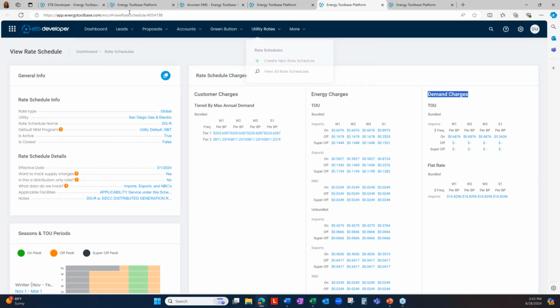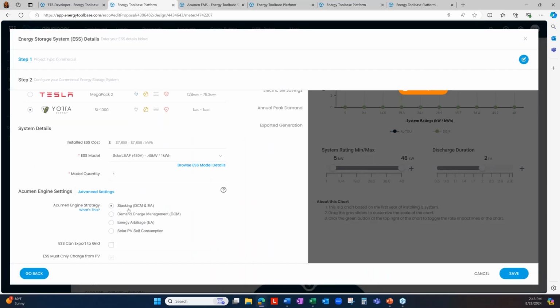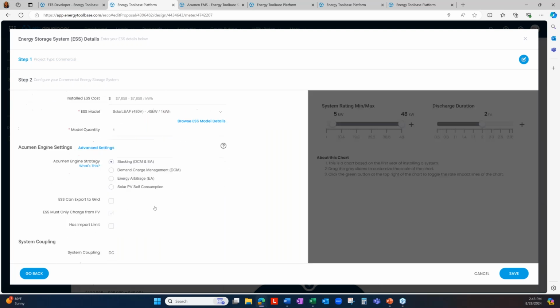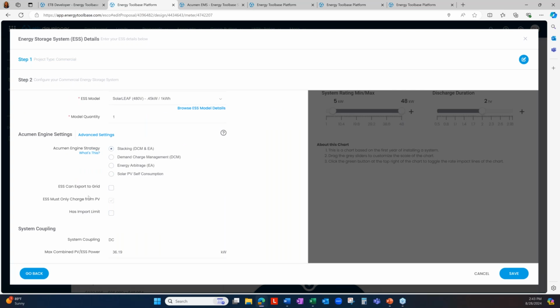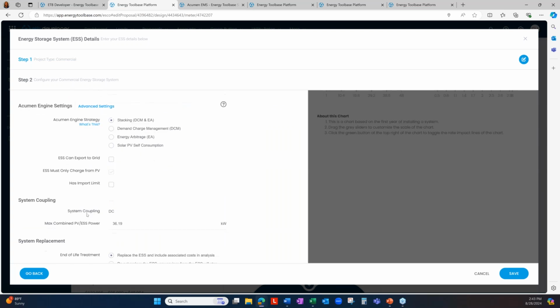So that's when I jump back into where we're at and choose stacking right here: demand charge management, energy arbitrage. You can select a number of other settings, but remember that number I told you to remember for system coupling. You'd paste it in here from that nameplate rating, which is the max combined PV and ESS power.